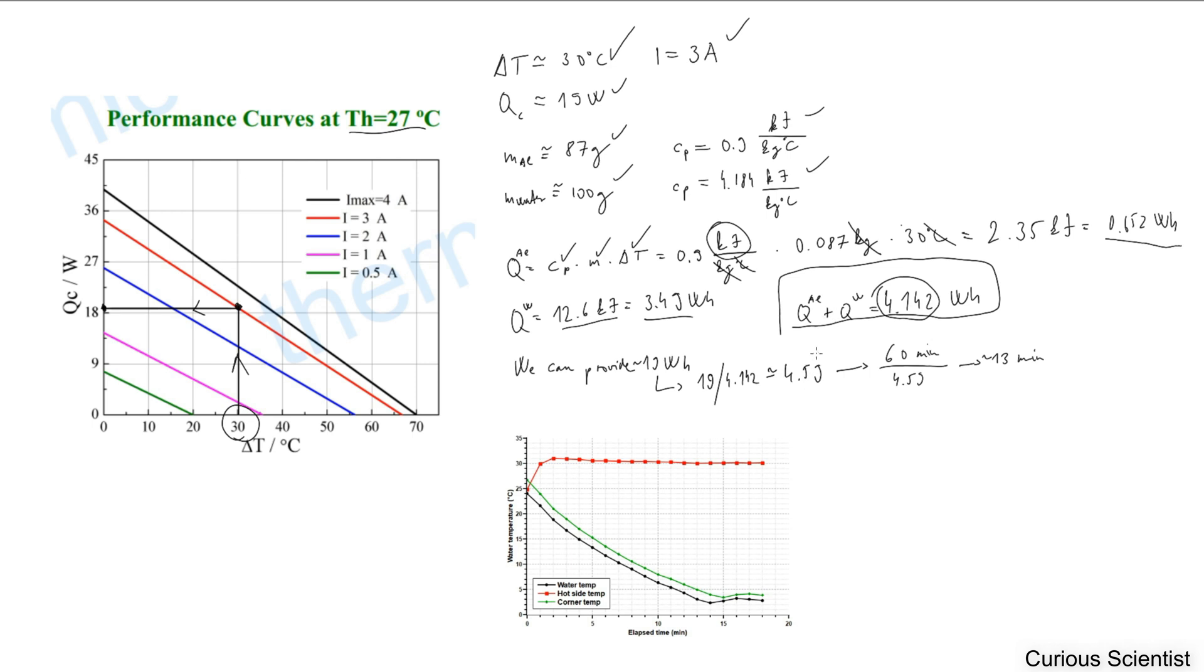You have to divide one hour or 60 minutes with this number, and you can get the time required to reach 30 degrees delta T. I did that division, so 60 minutes divided by 4.59, and that is roughly 13 minutes.